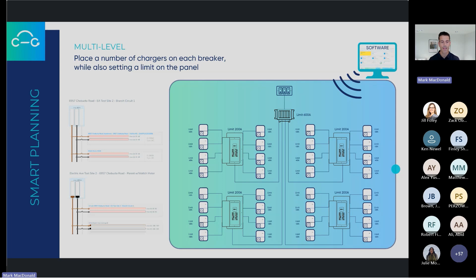So I could overload both in this scenario on the odd instance or really far down the road when we're starting to get a bunch of demand on the chargers on that building. So I can actually protect both. We call this a multi-level load share, where there's a transformer protected, but also the individual panels are protected, where this practically is the most valuable and what the NEC now recognizes. So I mentioned before, one charger equals 48 amps of load added to the building. If I do a 4-to-1 load share, I've only added 48 amps with 4.